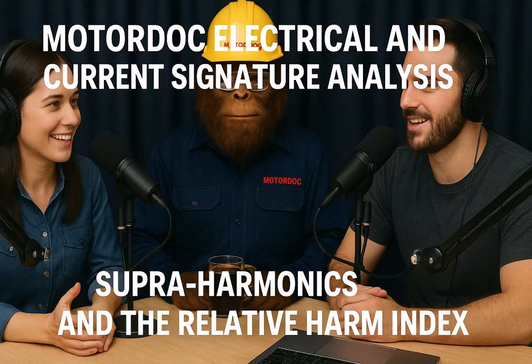Yeah. William Thomson first flagged a specific signature thought to be winding shorts, but later research clarified it. It's actually more an indicator of winding stress. Stress, not a direct short. Exactly. Electrical stress between the turns in a coil. Now, high stress isn't a short, but it can definitely lead to insulation breaking down and eventual failure, especially, as you mentioned, with VFDs involved. Okay.